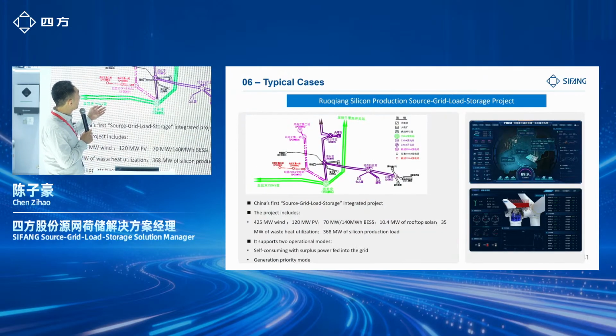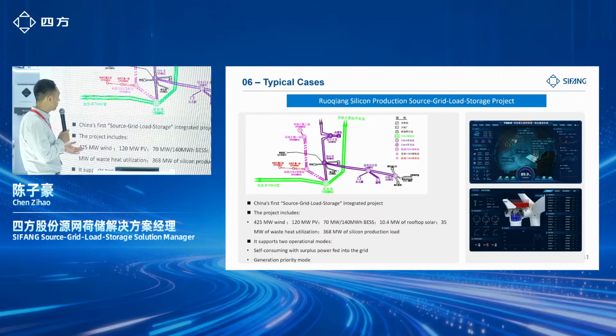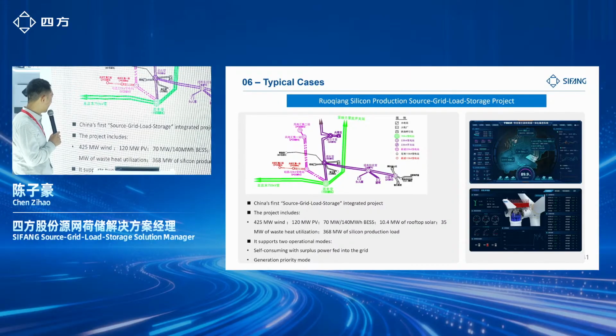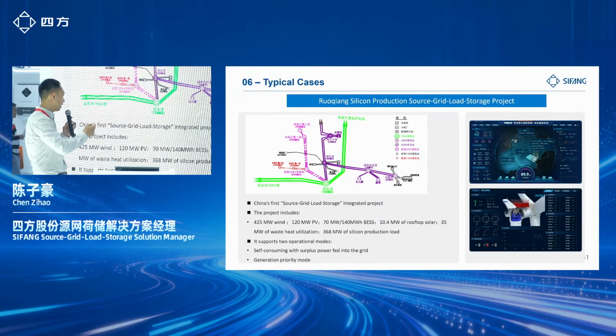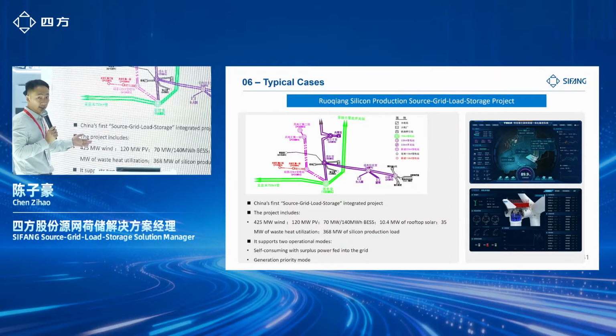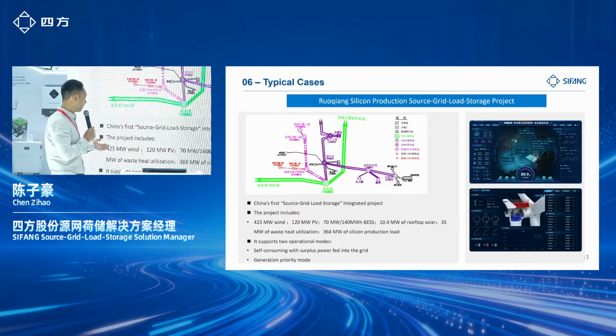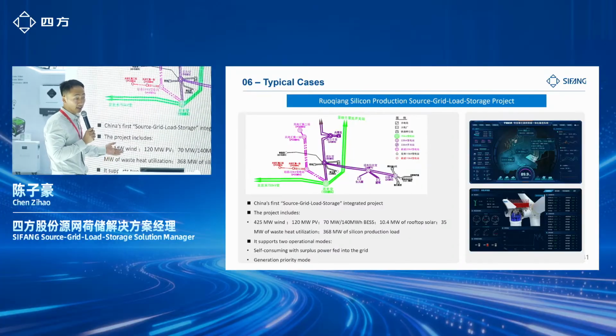And this is another source grid load storage scenario project. This is China's first SGLS integrated project, and the whole project includes 425 megawatts wind, 120 megawatts PV, also the rooftop solar and the BESS system. And it mainly operates in two modes. The first is self-consuming with surplus power feeding to the grid. The second is the generation priority mode.